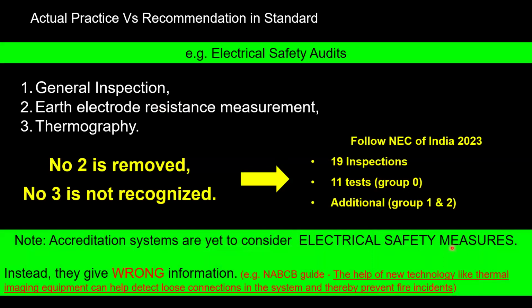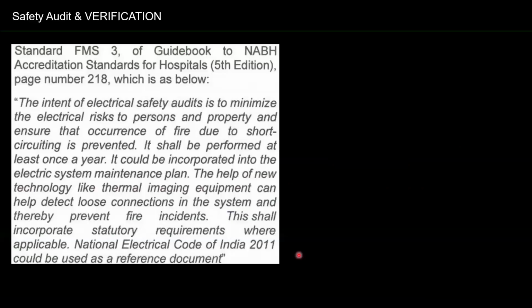So far, there are some wordings where the management should keep the electrical system safe. That's all, but the process recommended gives wrong information. For example, in the NABCB guide, it's written that new technology like thermal imaging equipment can help detect loose connections in the system, thereby preventing fire incidents. Unfortunately, this is not the correct way.